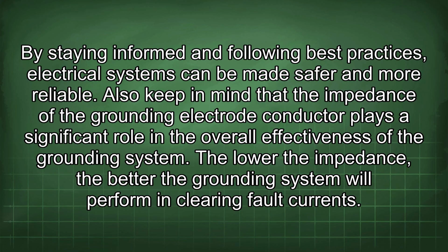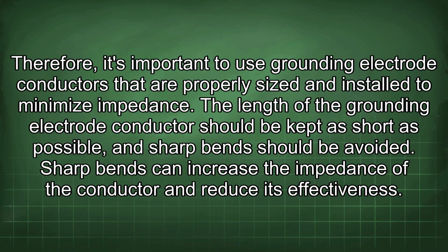Also keep in mind that the impedance of the grounding electrode conductor plays a significant role in the overall effectiveness of the grounding system. The lower the impedance, the better the grounding system will perform in clearing fault currents. Therefore, it's important to use grounding electrode conductors that are properly sized and installed to minimize impedance. The length of the grounding electrode conductor should be kept as short as possible, and sharp bends should be avoided. Sharp bends can increase the impedance of the conductor and reduce its effectiveness.